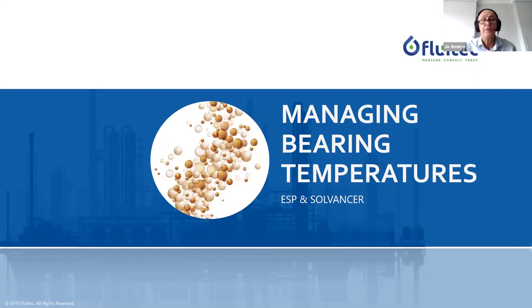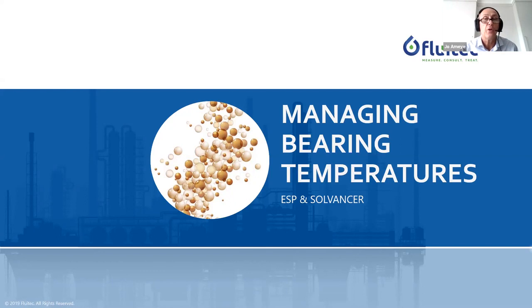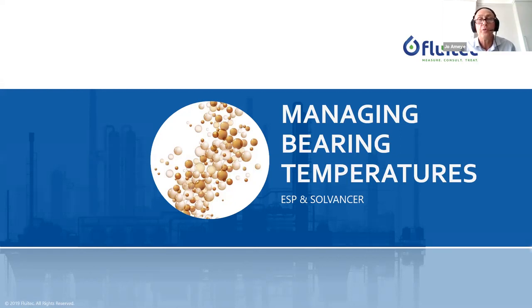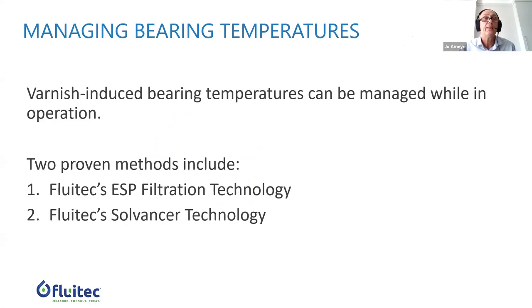We receive the question: can we do something about this? Of course you can monitor bearing temperatures or perform visual control. The number one reaction should be to make sure you have done the right oil analysis — we can discuss that in later sessions highlighting the importance of oil analysis. Besides detecting the presence of varnish, is there anything you can do to avoid a further increase of bearing temperatures? For a lot of operators, reaching this high bearing temperature usually means the equipment has to go out of service — that is the last thing operators want to see.